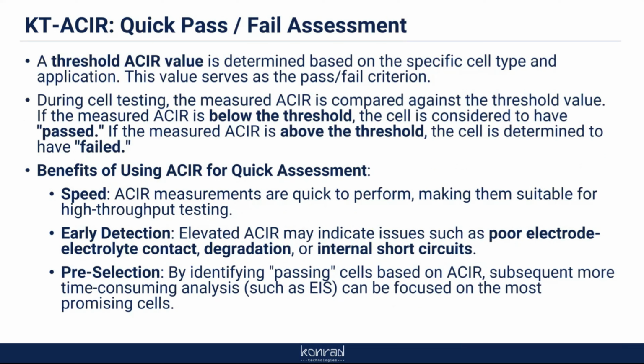What we typically use ACIR for is as a prelude to an EIS measurement, which we're going to talk about in a minute. Usually you would have a threshold ACIR value or a threshold OCV value to decide whether a cell is even worth further testing, because you can finish that measurement very quickly. If either the ACIR value or the OCV value is out of spec, then you fail the part. So obviously very fast. ACIR can be done early in cell formation, so you can often catch problems quickly and not add any more value to that cell. So that's the main goal of that.